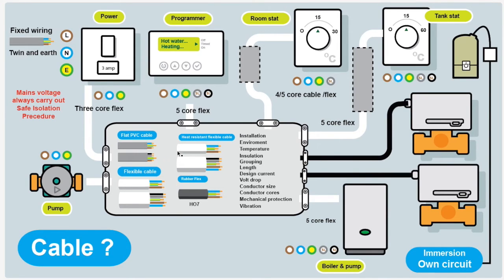You've got your fixed wiring and your flexible wiring. The immersion heater for example, this is an example where you use both types of cable. You're going to use the flat PVC for your fixed wire installation. This is the cable coming from your fuse board. That's your flat PVC cable which is run to the switch. Then from the switch you'd run that in flex cable. Cable clamped at both ends. It's perfectly safe. So make sure you use the right type of flex.